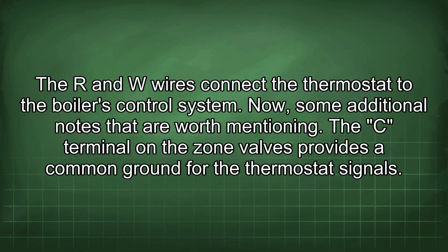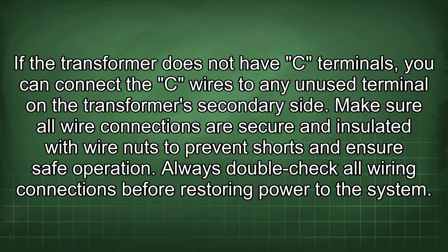Now, some additional notes that are worth mentioning. The C terminal on the zone valves provides a common ground for the thermostat signals. If the transformer does not have C terminals, you can connect the C wires to any unused terminal on the transformer secondary side. Make sure all wire connections are secure and insulated with wire nuts to prevent shorts and ensure safe operation. Always double-check all wiring connections before restoring power to the system.